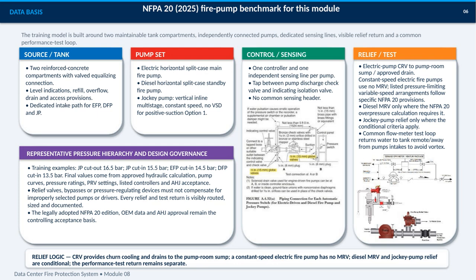The source arrangement includes equalizing refill, overflow, drain, access, and level provisions with dedicated intake paths for each pump. The pump set uses an electric horizontal split case main pump, a diesel standby pump, and a constant speed vertical inline multistage jockey pump for the positive suction option described here. Each pump has its own controller and sensing line, tapped at the specified discharge location, rather than using a common sensing header. Relief and testing are deliberately separated.